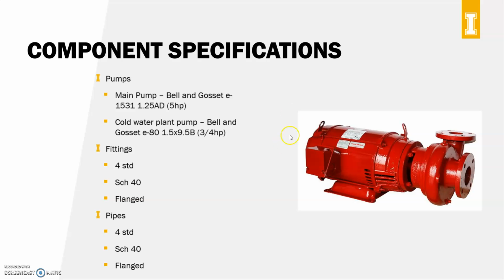Now, I said I would talk about the pumps we chose. Our main pump, the one doing the main line all the way from the CNR basement up the hill, is a Bell & Gossett E1531 1.25 AD, and this is the 5 horsepower model. The 5 horsepower model we determined was the one we would need to provide the suitable head.